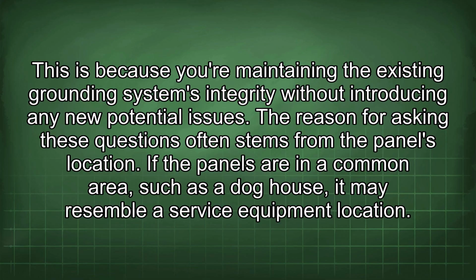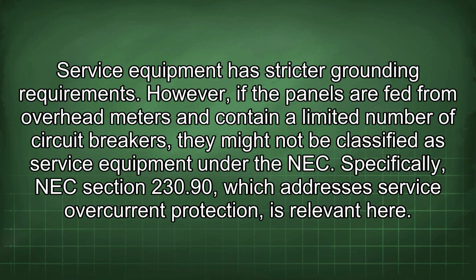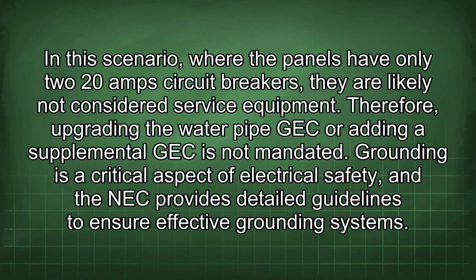The reason for asking these questions often stems from the panel's location. If the panels are in a common area, such as a dog house, it may resemble a service equipment location. Service equipment has stricter grounding requirements. However, if the panels are fed from overhead meters and contain a limited number of circuit breakers, they might not be classified as service equipment under the NEC. Specifically, NEC Section 230.71, which addresses service disconnect grouping, is relevant here. In this scenario, where the panels have only two 20-amp circuit breakers, they are likely not considered service equipment. Therefore, upgrading the water pipe GEC or adding a supplemental GEC is not mandated.